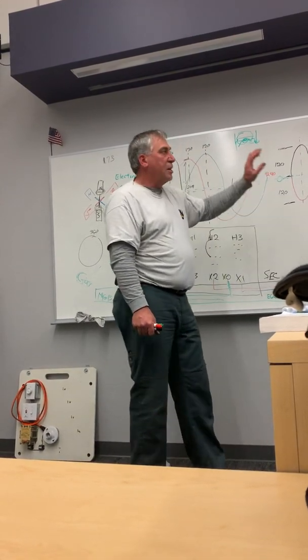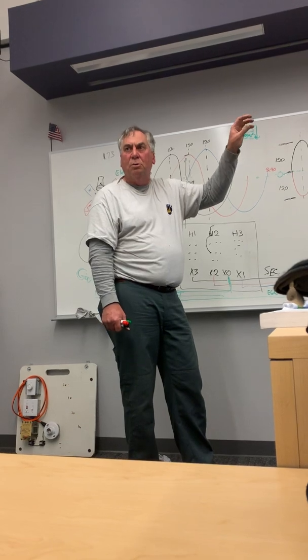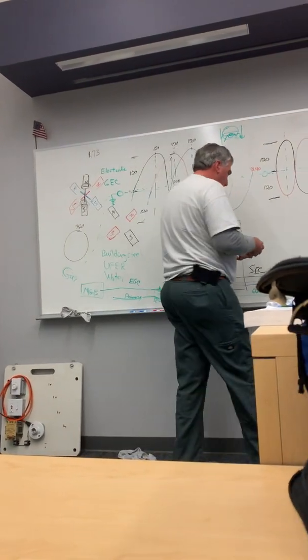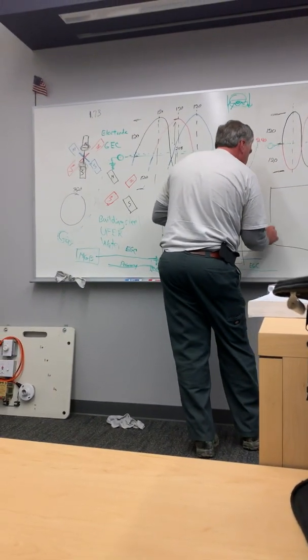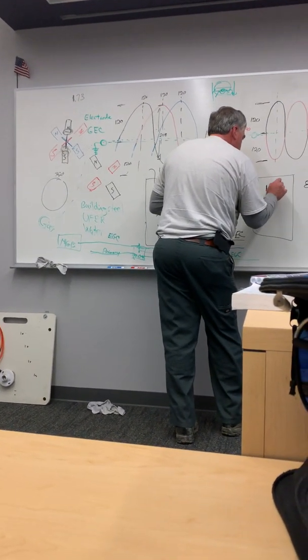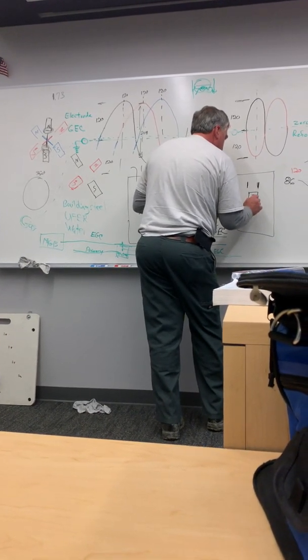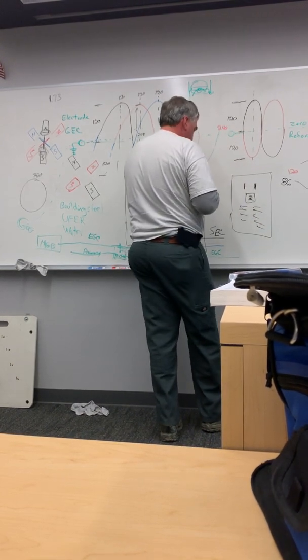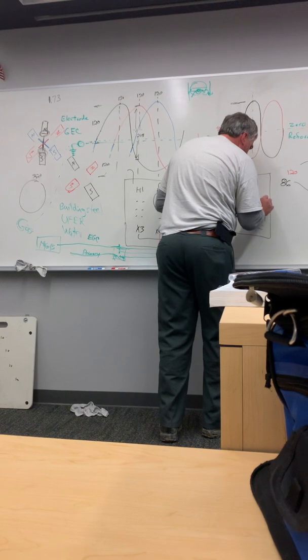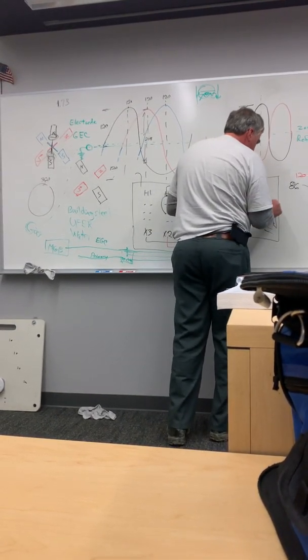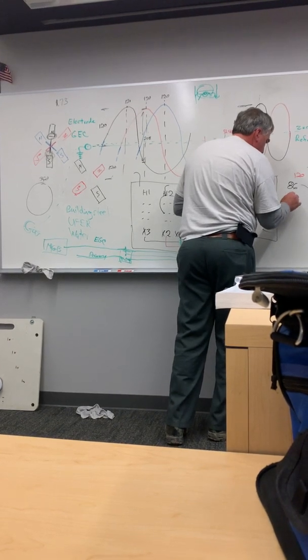When you have a service entrance panel coming into a building, you ever see those disconnects? They come out, it's a little 100 amp disconnect with its two wires, maybe a main breaker in there, and all its branch circuits. But it's kind of weird, because the neutral bar is here, but it's got a tapped screw in it, and this big long green screw.